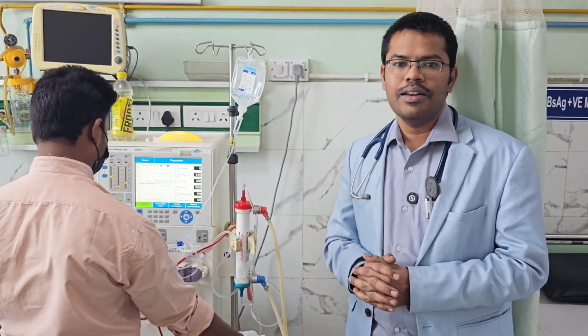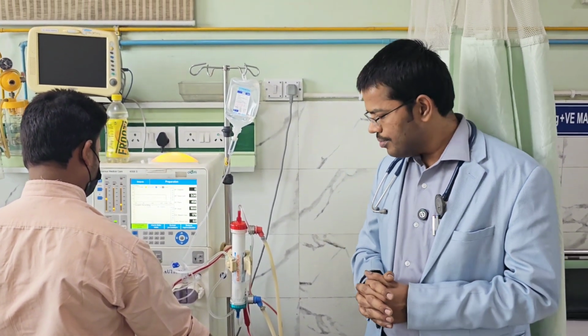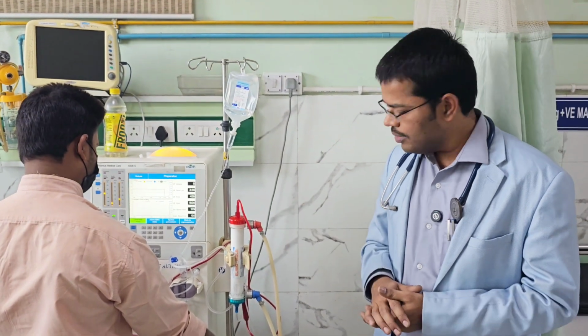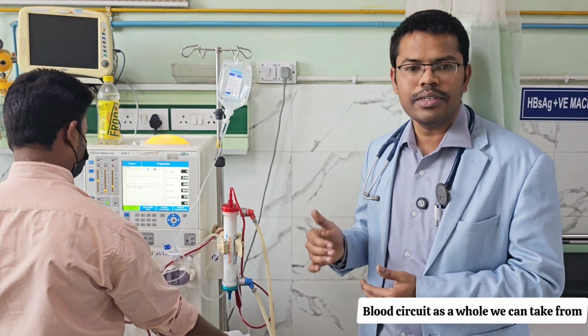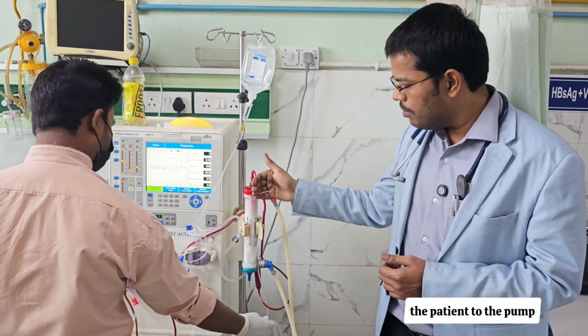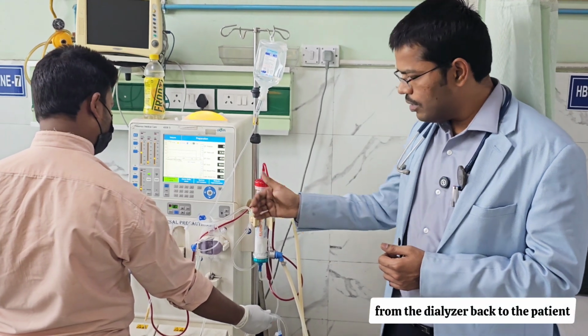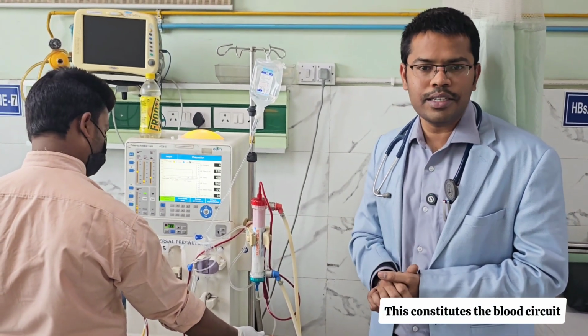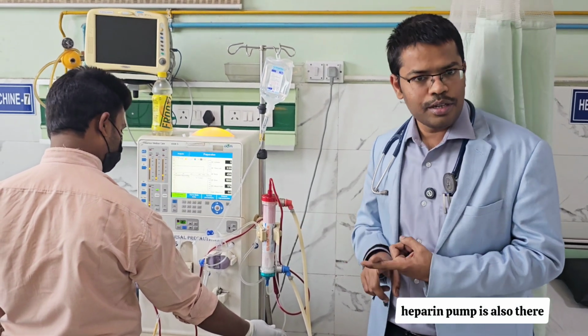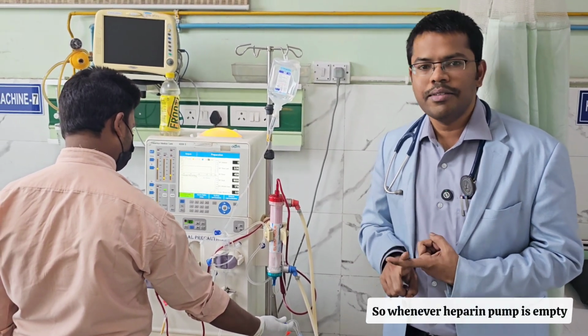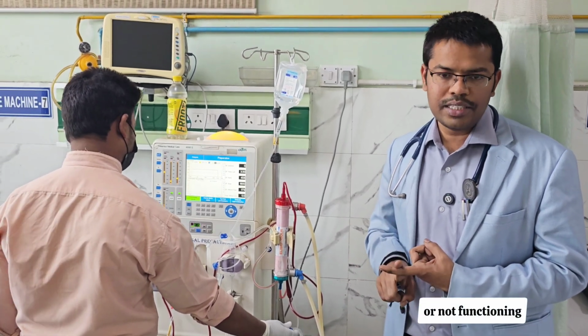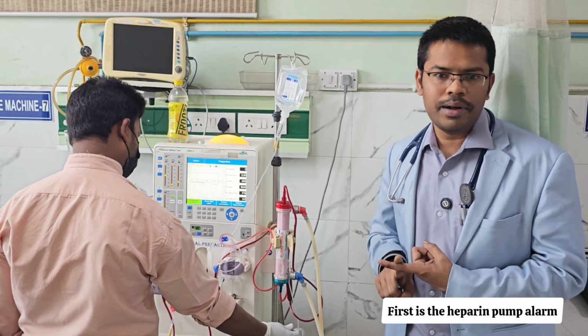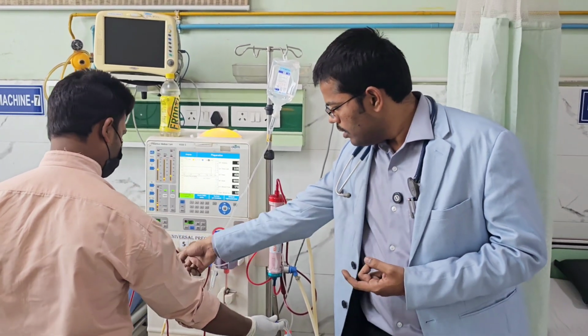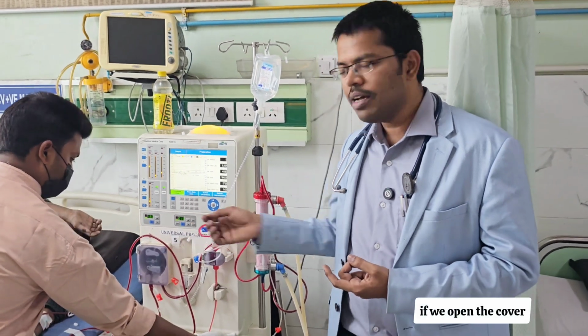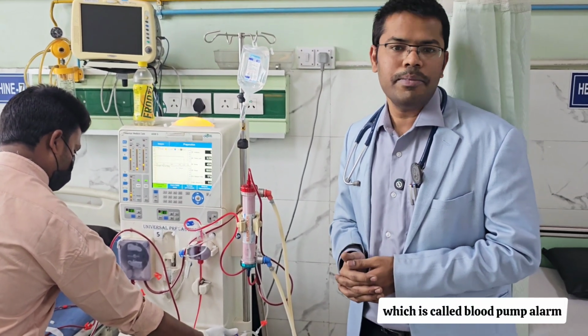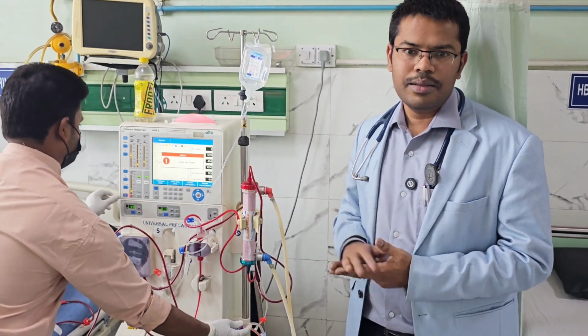Now coming to the blood circuit alarms. Now the machine is being connected. The blood circuit as a whole we can take as from the patient to the pump, from the pump to the dialyzer, and from the dialyzer back to the patient. This constitutes the blood circuit. In that, the heparin pump is also there, and the blood pump is also there. Whenever the heparin pump is empty or not functioning, the alarm will ring. First is the heparin pump alarm. Second is the blood pump alarm. If we open the cover of the blood pump, the alarm will ring. Any issue, you open it, the blood pump alarm will ring.